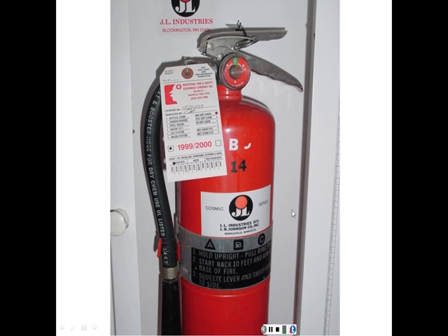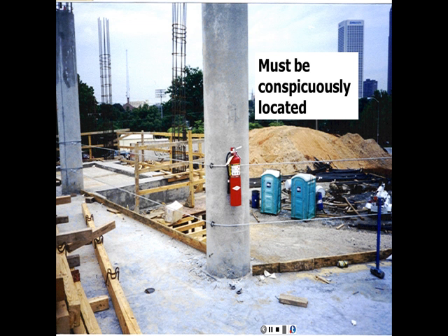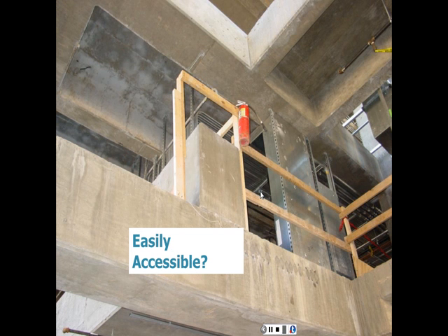Here we have a B, actually it's a B and C, but the C has been torn or erased from that extinguisher. It shows what kind of fires it can resist, and it shows its capacity, when it was inspected, who inspected it, and so on and so forth. So it shows that it's ready for use. It must be conspicuously located, so here you can clearly see it on site, and easily accessible on any floor, as we mentioned before.